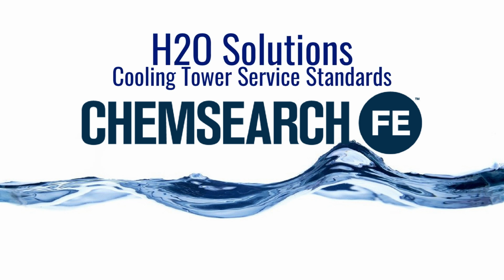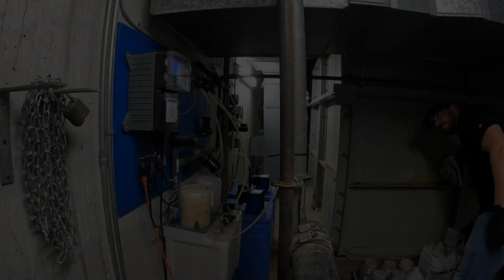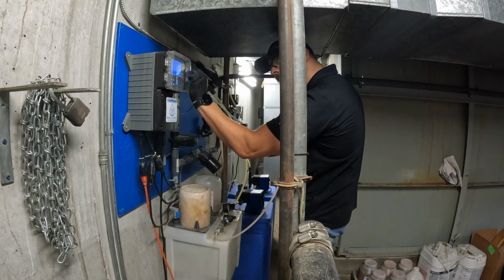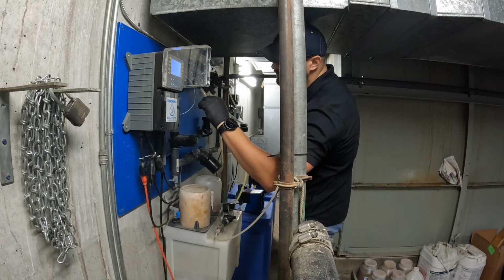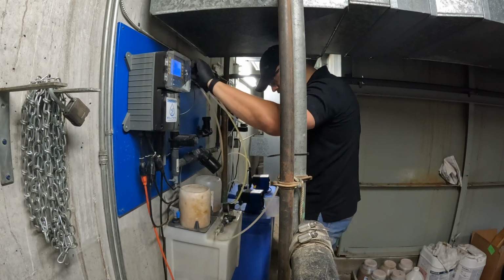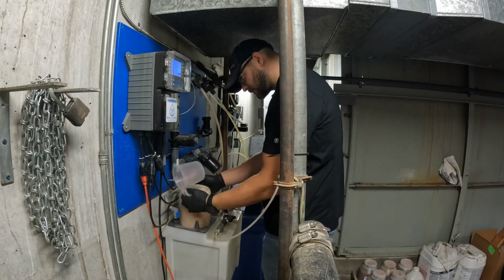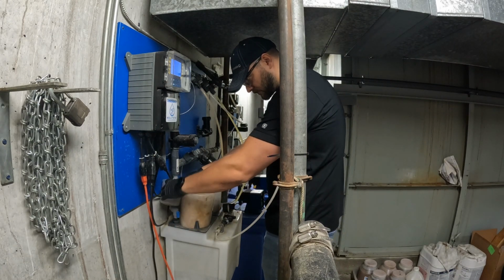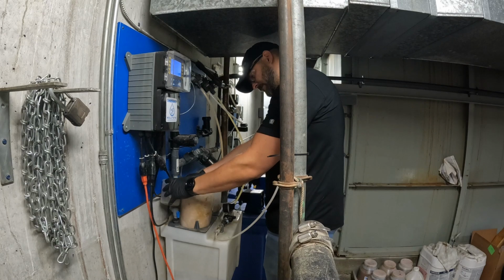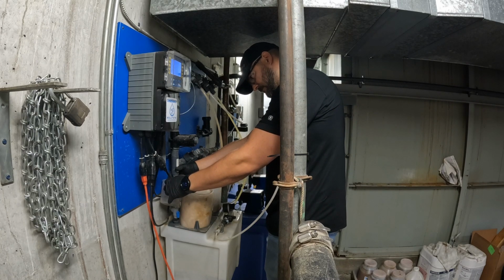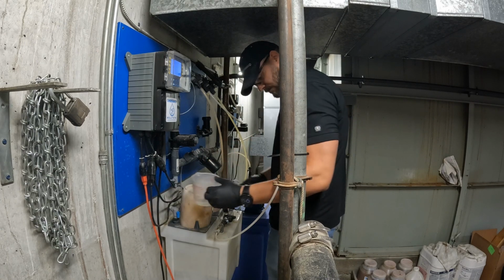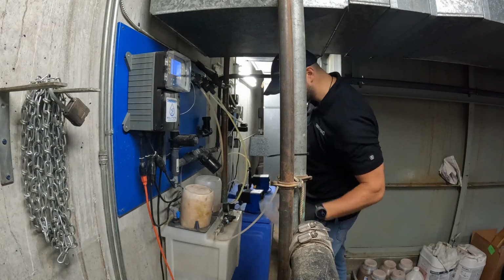In today's video, we will show what a standard cooling tower service visit should look like. Your first step will be to check the controller to make sure there are no immediate issues. Once you have confirmed there are no problems, you can collect your cooling tower sample. You also need to collect your makeup water sample before testing. Be sure to triple rinse your samples to avoid any contaminants. Once collected, you can set it aside for testing.